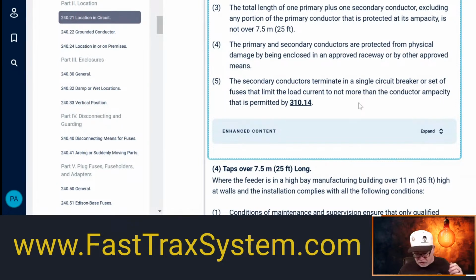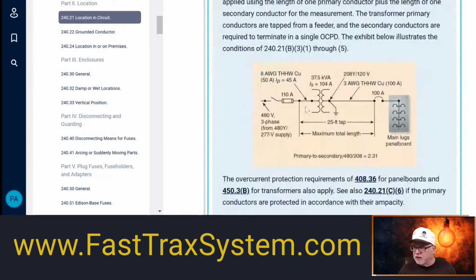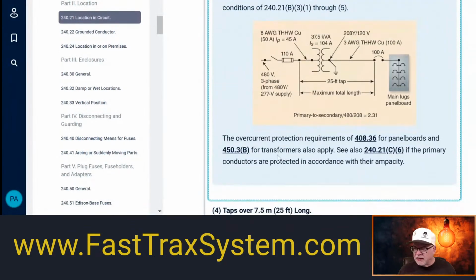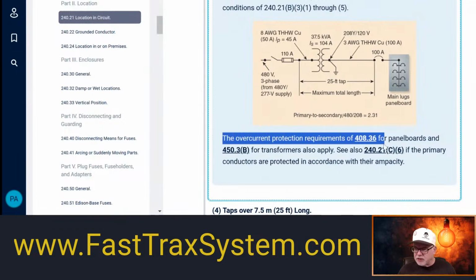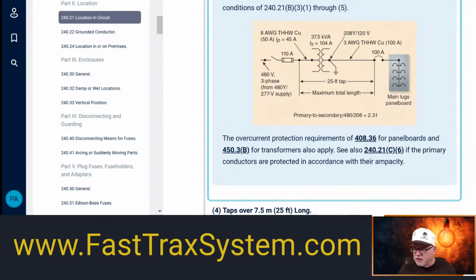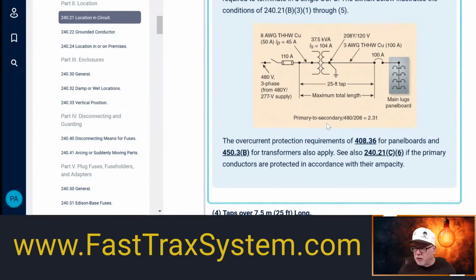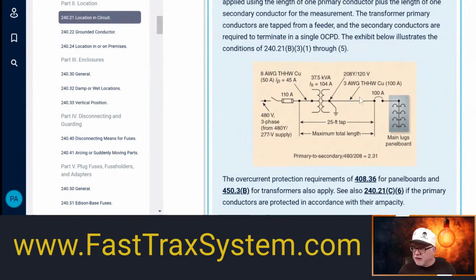So those conductors, again, when you size them, you have to make sure that that circuit breaker is going to be equal to or less than whatever the conductor rating is, because we have to make sure that those conductors are protected, okay? Now, there is an enhanced drawing here that's easy for you to follow, and again, this makes the reference to 408.36, which is this panelboard protection, okay? That you have to be aware of, and there are some allowances in there.